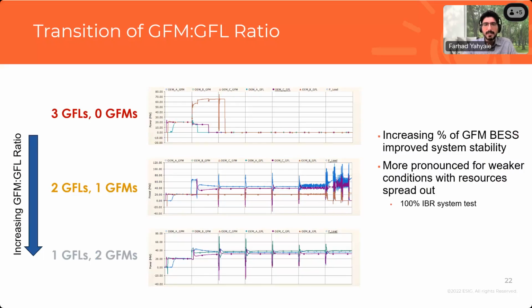We ran a different study where the ratio of GFM to GFL was changed. In the earlier scenario with three GFL models, when faults were applied, the top plot shows the system collapsing, meaning the GFL models aren't able to sustain or preserve system stability. Once we increased the amount of GFM, either by number or per-unitized values, we saw more stable behavior.